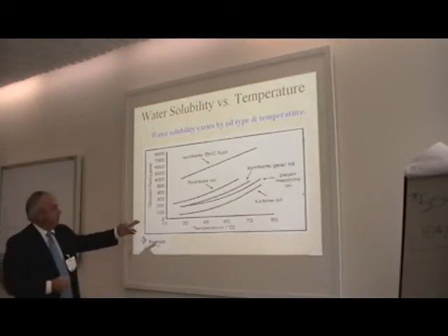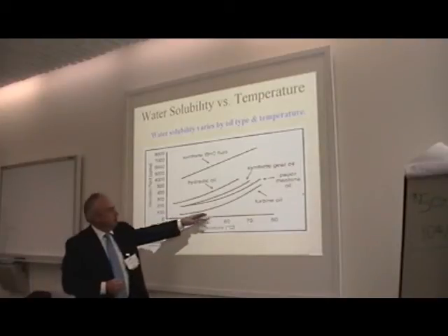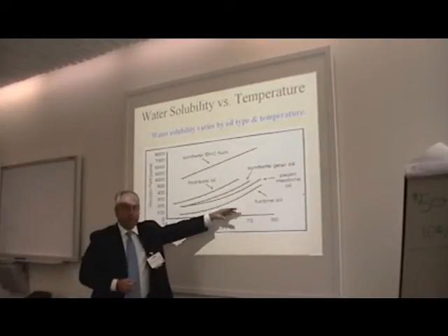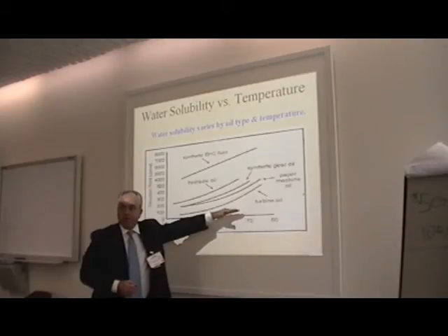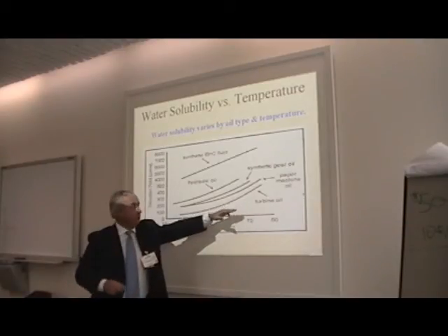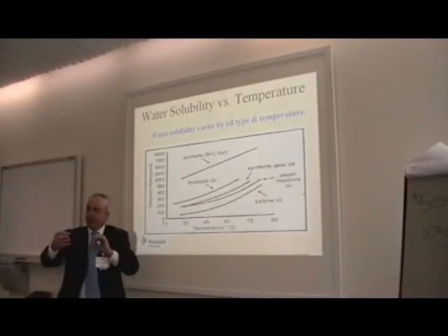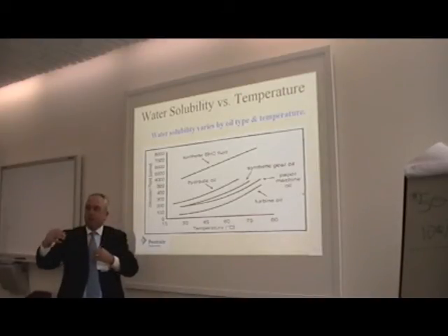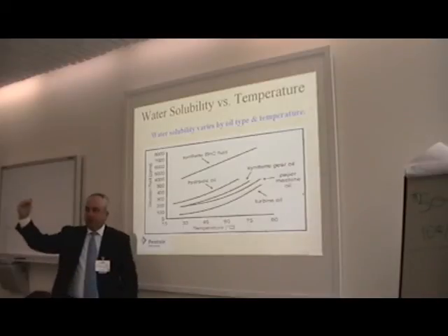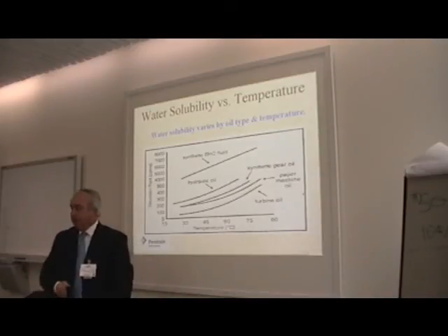Again, with turbine oils, you do want to make sure you're getting sufficiently below saturation, as in the best example, down to about 40 ppm in this case. If this unit is cycling on and off service, when that oil cools back down to room temperature, you'd have condensing water again. When a machine is running hot, the moisture's all dissolved into the oil, it's kind of out of the way. When you shut it down, the machine cools off, and you'll actually start condensing the moisture inside the gear, inside the turbine itself, which is obviously going to lead to corrosion.